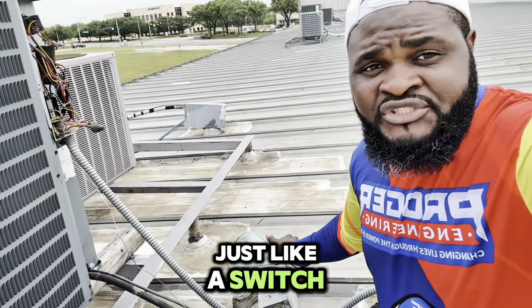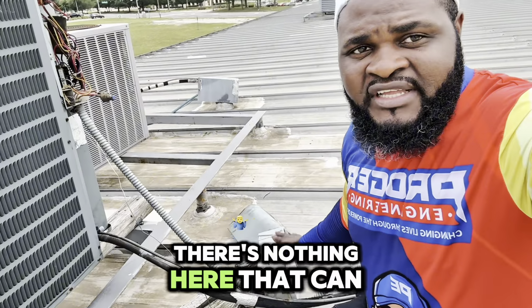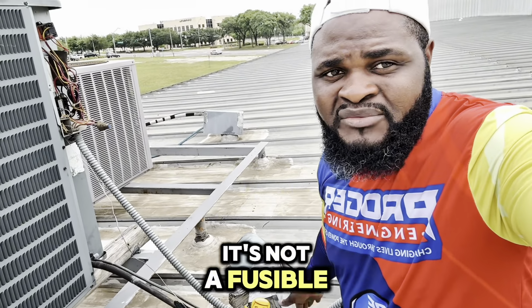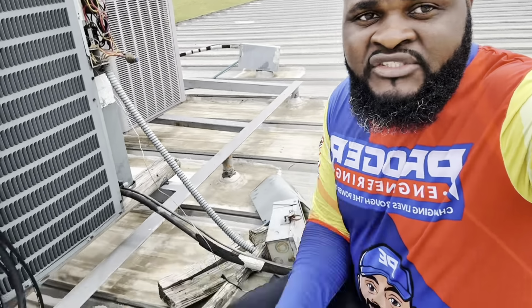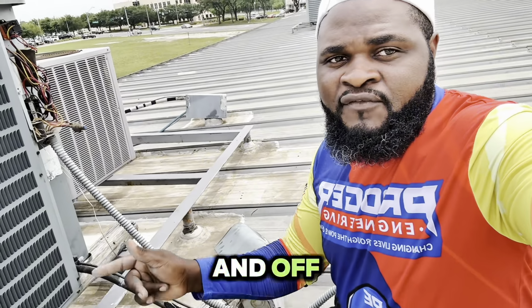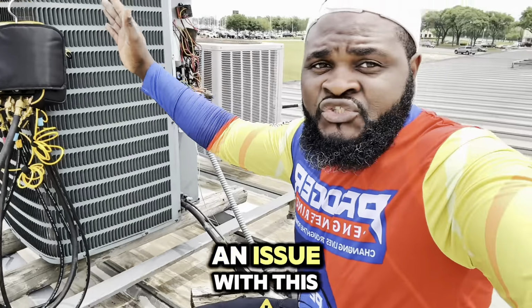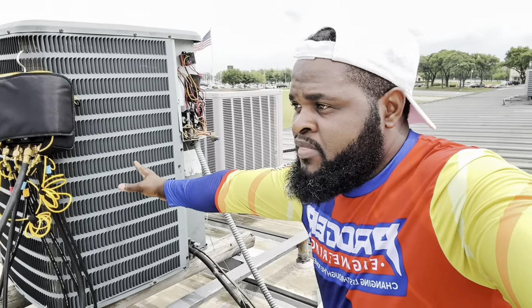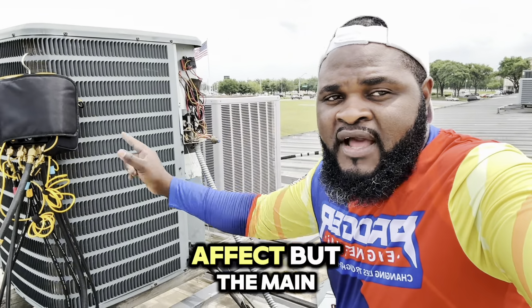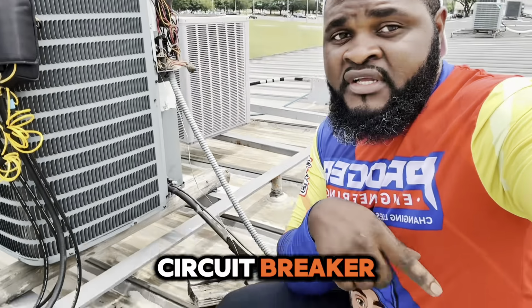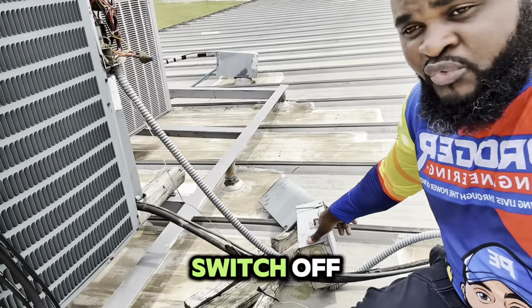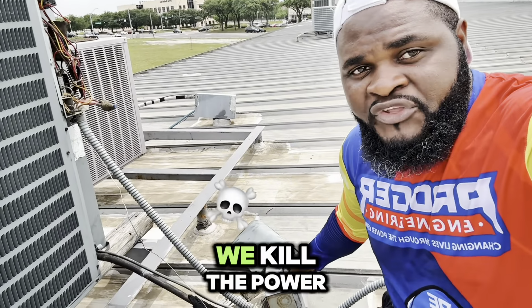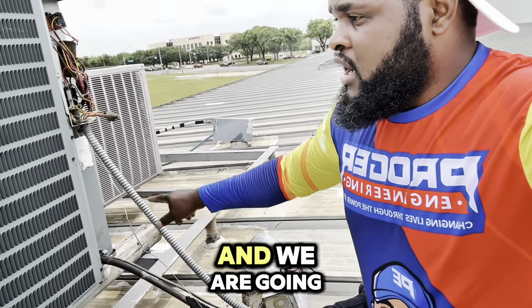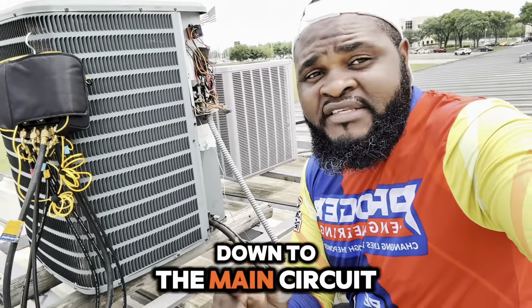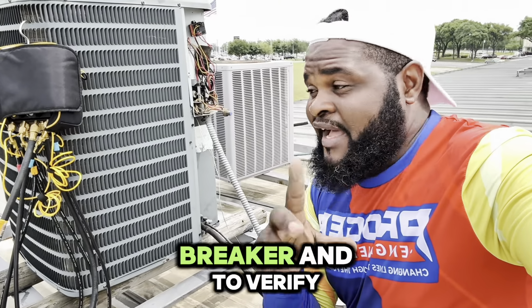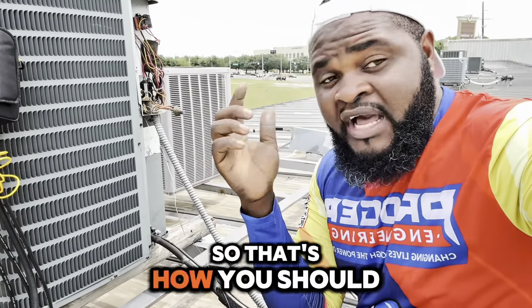This is just like a switch. There's nothing here that can protect this. It's not a fusible disconnect or anything. It's just like a switch to power on and off. So definitely if there's an issue with this unit here, it would affect the main circuit breaker. That's why we turn this switch off, we kill the power, and we are going now to the main circuit breaker to verify. So that's how you should do it.